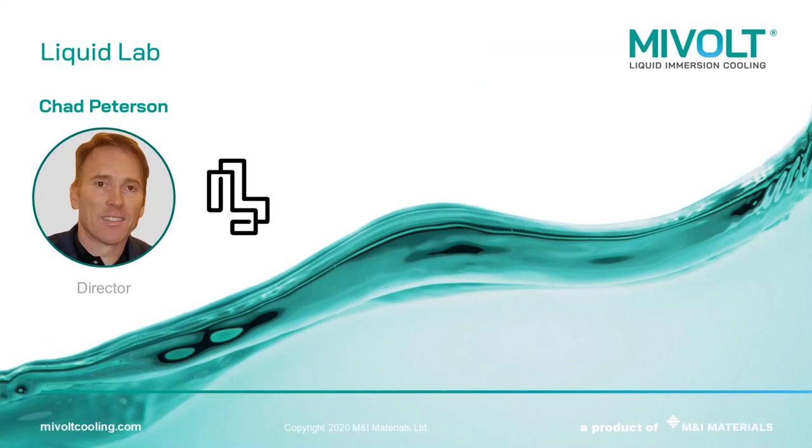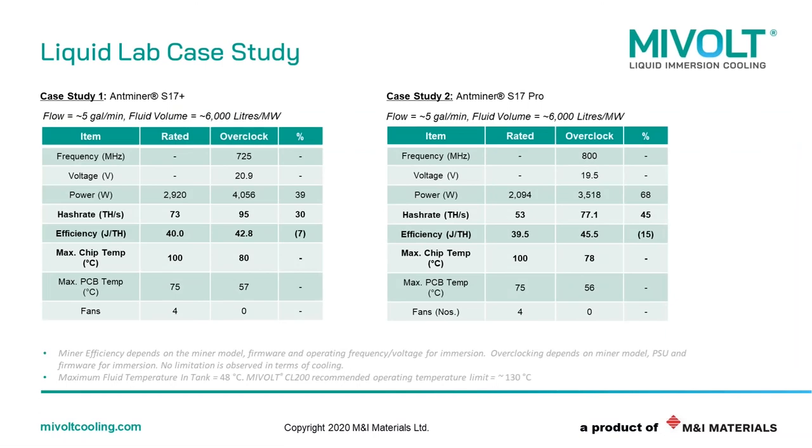Thank you, Rob. It's good to be here today to talk about MIVOLT. It's been a long time search for Liquid Lab to find a fluid that actually works, that isn't expensive and doesn't evaporate all your profits into the atmosphere. We've been working for the last three years testing and designing immersion cooling systems, and before that, strictly air cooling. We've used 3M fluids, two-phase fluids as Rob suggested — Novec 7100, Novec FC72 — and then switched to single-phase fluids, synthetic PAOs, synthetic motor oil even. And finally we discovered MIVOLT and have concentrated exclusively on that.